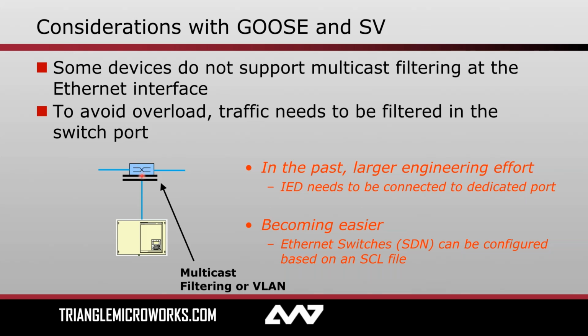The first one is that you're probably going to be configuring a single port to have the relevant GOOSE or sample values messages passed out of it down to this IED. So if you come along and move this Ethernet or fiber optic cable over to a different port, you could break something. The other thing to keep in mind is that there's a lot of extra configuration that goes into this, but this is an area that's changing rapidly. There's a lot of work being done by vendors who create switches in order to make this easier.